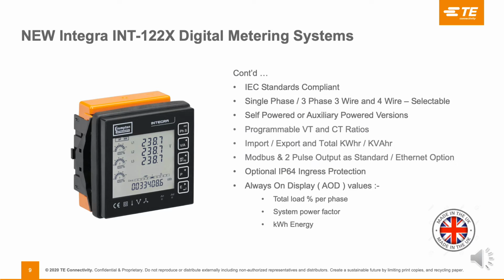Some additional features for the product. It is designed and manufactured to be IEC standards compliant. It has the facility of programming the meter to be single phase, 3-phase 3-wire and 3-phase 4-wire. It can be self-powered or alternatively have an auxiliary powered version. The VT and the CT ratios can be programmed into the meter, so this can be used for say 132, 33 or 11 kV or even 415 volt on the low voltage. CT ratios are programmable with a secondary of 1 amp or 5 amp.